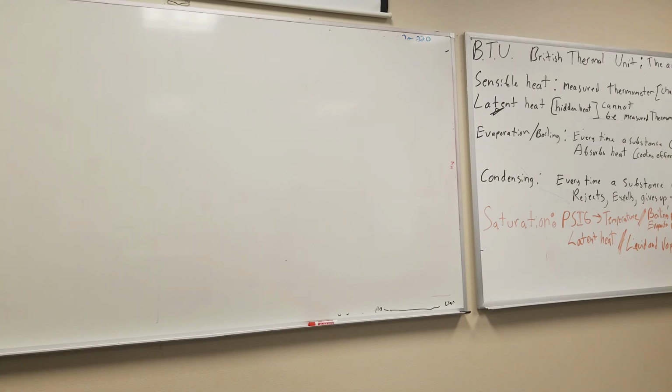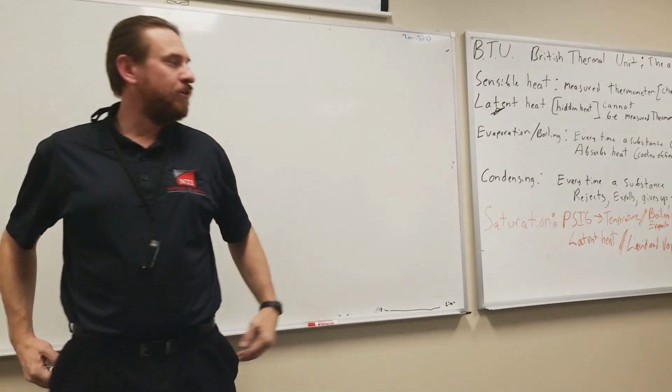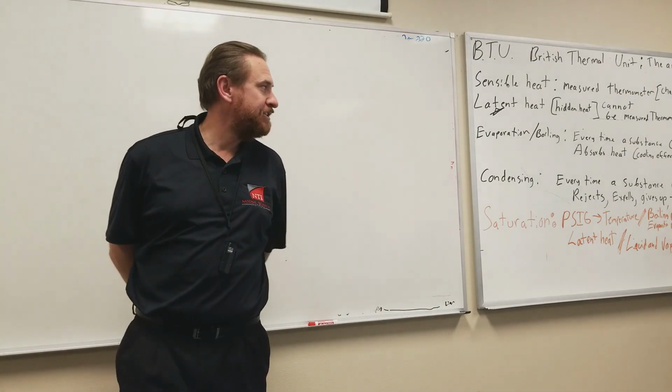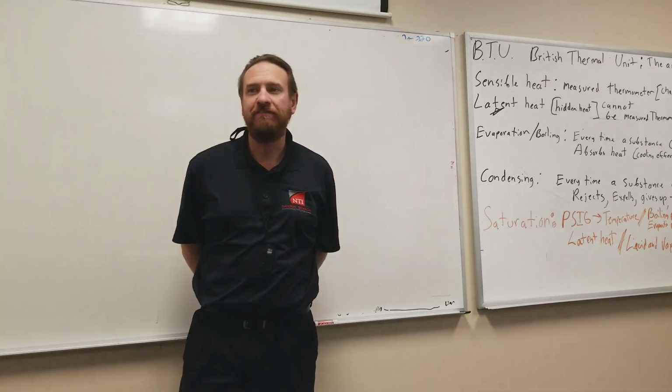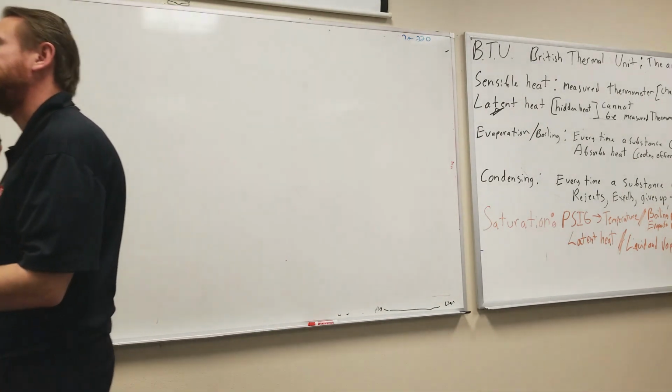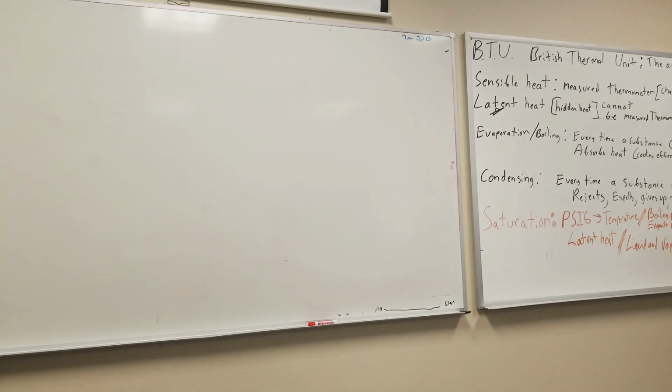So when you talk about measuring it, you're only talking about the amount of heat you're putting into it. Right. So basically, if it's saturated, it's the same temperature. Yes, that's right. So when it's boiling in the evaporator, it's PSIG converted to temperature. Taking that PSIG and converting it to temperature is telling us where saturation's at. It's giving us a starting point.